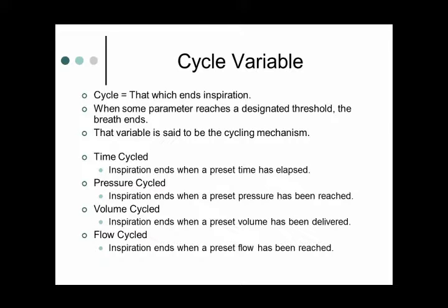A lot of people, including me, and I catch myself, will say it's the ventilator's auto cycling. No, the ventilator's auto triggering. Cycling means ending the breath, not starting it. I just said it five minutes ago. Just gotta be careful. That parameter with which some criterion is met turns it off. So it could be time cycled. My breath ends because a certain amount of time has elapsed.